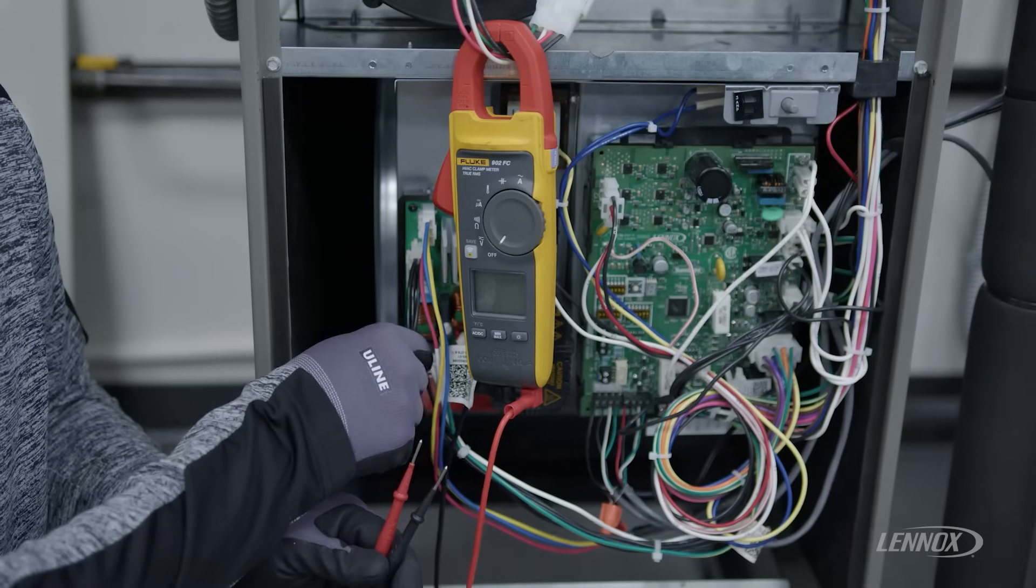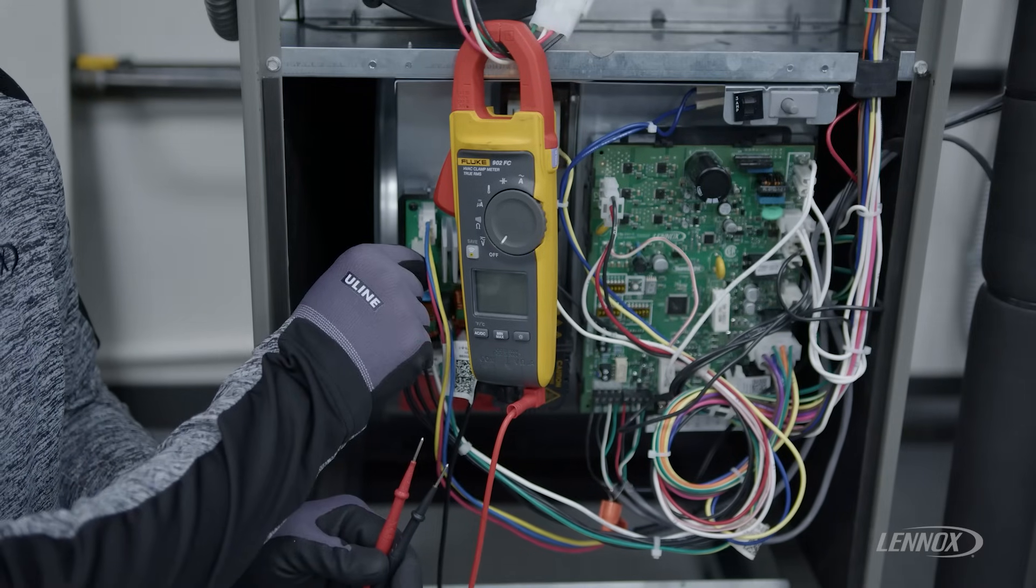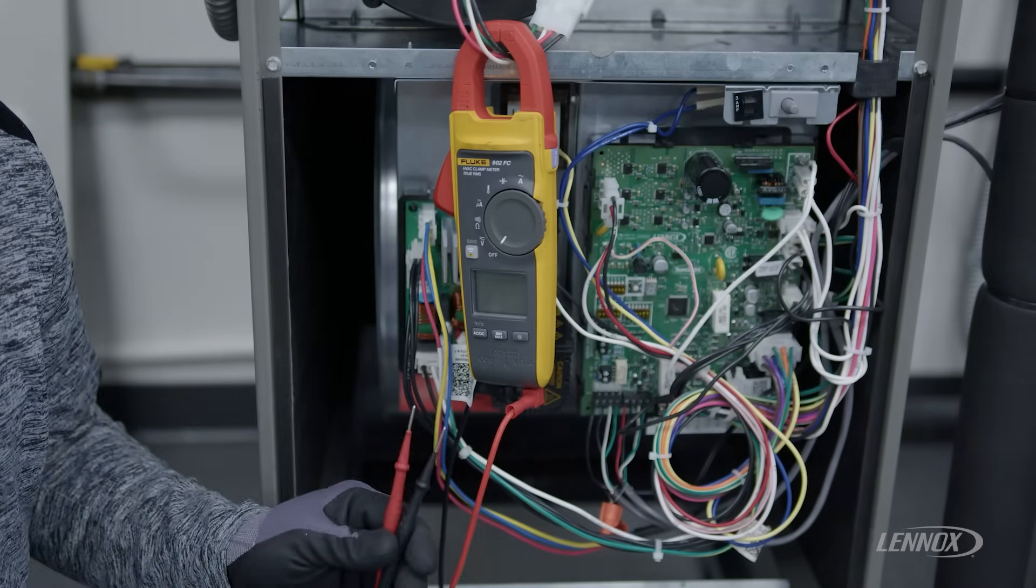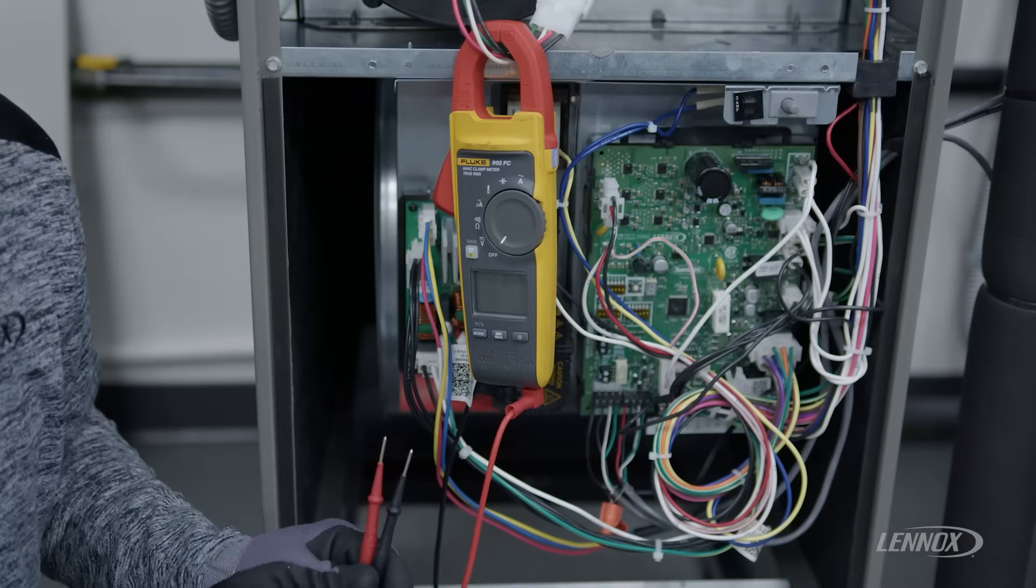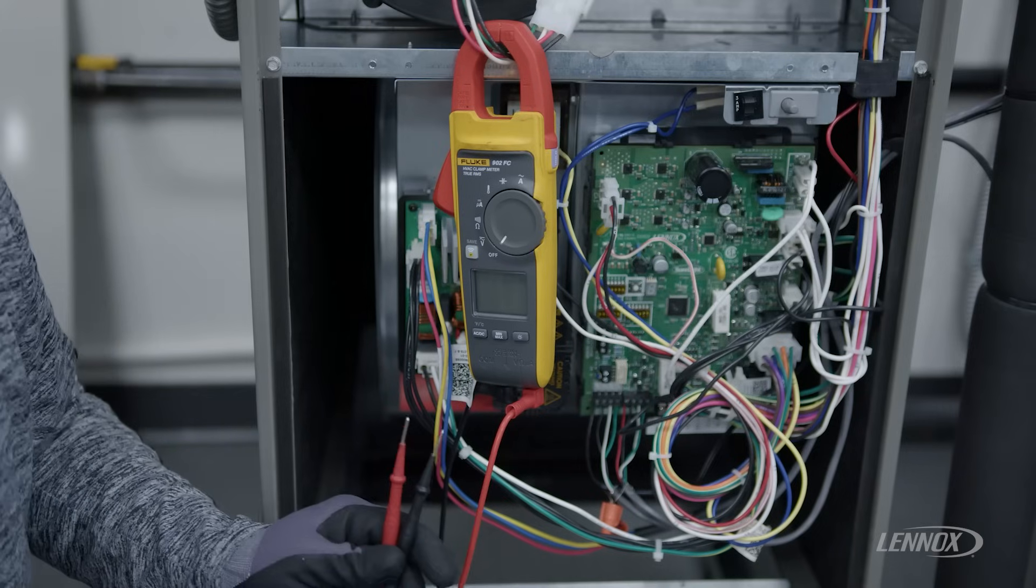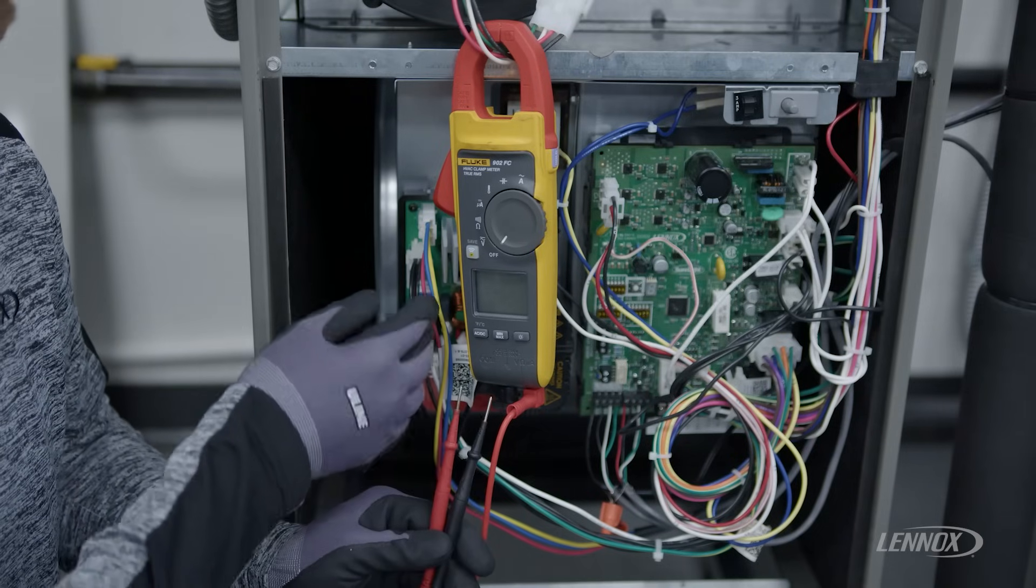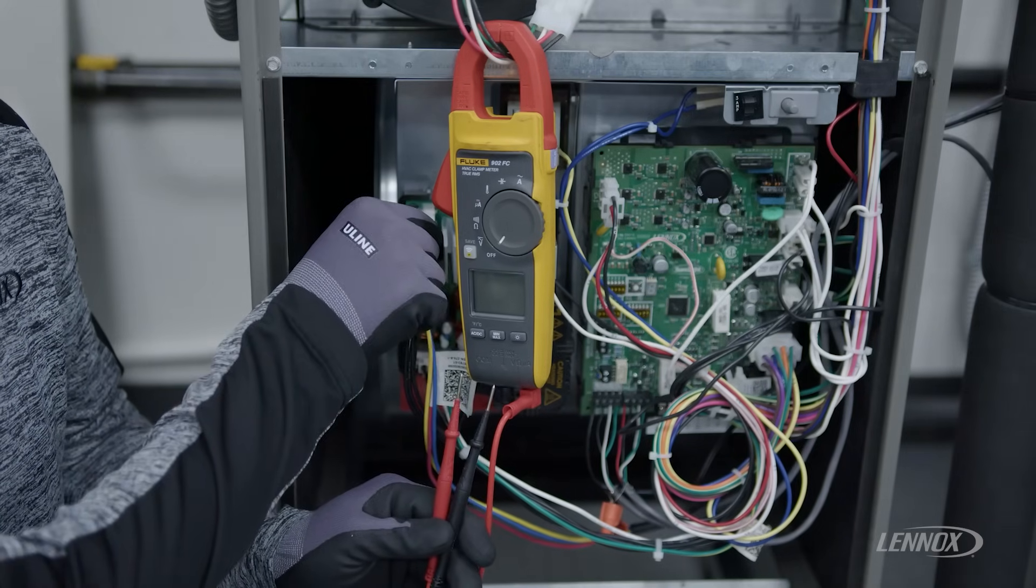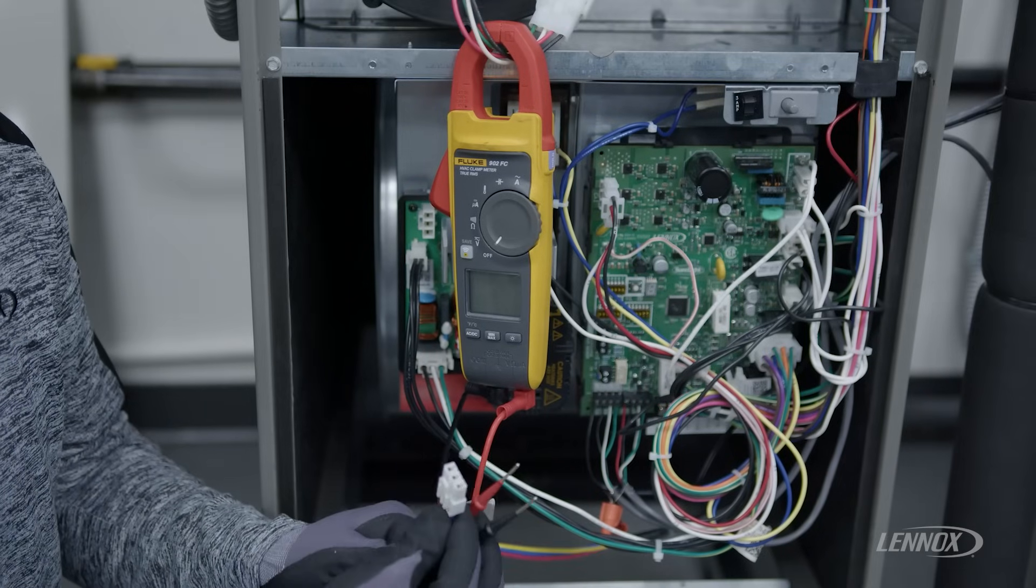Once we've confirmed the integrity of the communication wire, ensuring that it's plugged in and tightly secured and there's no evidence of corrosion, we could then move on to a motor check. To do this, simply come to our motor drive board, remove your 3-pin harness that connects to the motor.